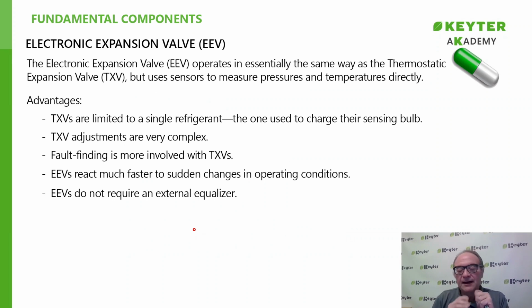It works like a thermostatic expansion valve, but the difference is that it works electronically by measuring pressures and temperatures, so its management is much faster, and it has a series of advantages over the thermostatic expansion valve, which, as we already said, was slow in its operation due to the way it is constructed. Thermostatic valves are only suitable for one refrigerant. The bulb is charged with a refrigerant, so that is what controls the thermostatic expansion valve, and it is only suitable for one refrigerant.